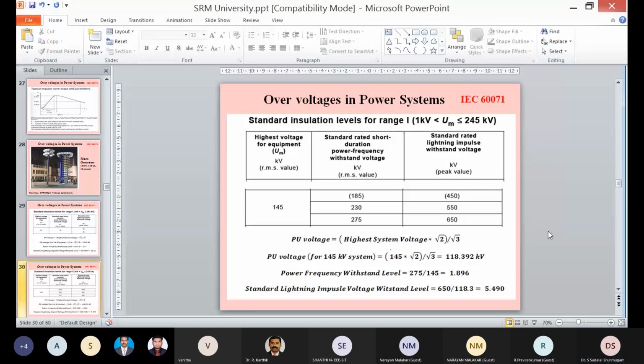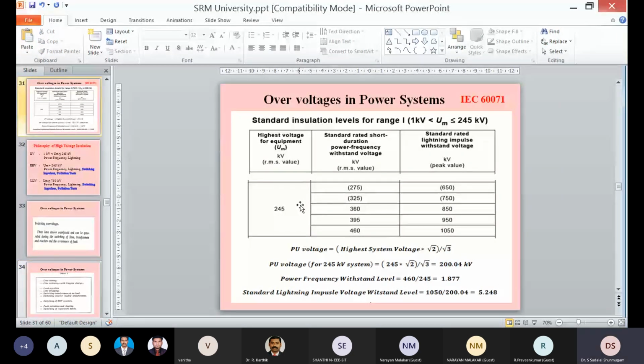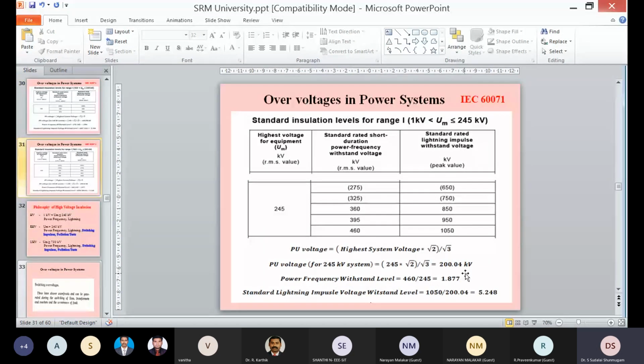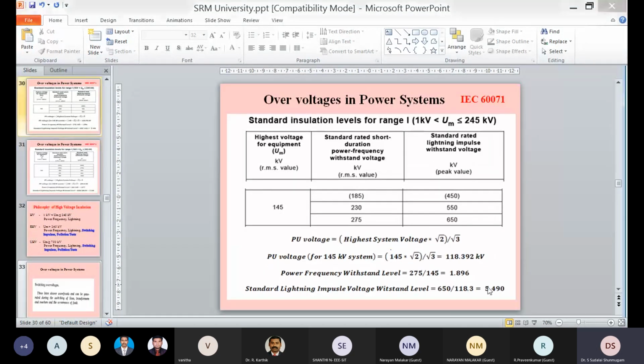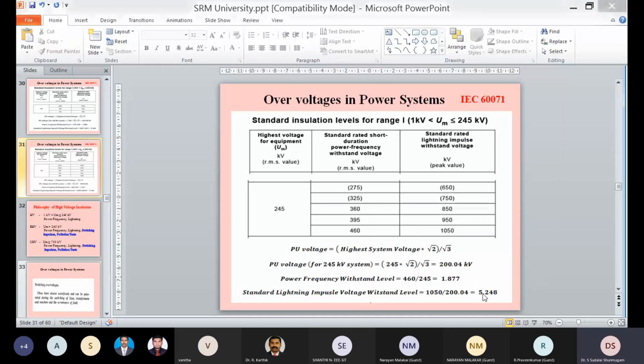I'm moving to the next slide. It is a 245 kV system. Again, a set of values is given for power frequency withstand voltage, and a set of values is given for lightning impulse voltage. For example, for a 245 kV system, per unit value is 200.04 kV. Power frequency withstand level is 1.87 times the highest system voltage, whereas standard lightning impulse voltage is only 5.24 times. If you see the earlier slide, it is 5.4 times. Now this is 5.24 times. Similarly, in the earlier slide, power frequency withstand level is 1.89 times the highest system voltage. Now it is again reduced to 1.87.